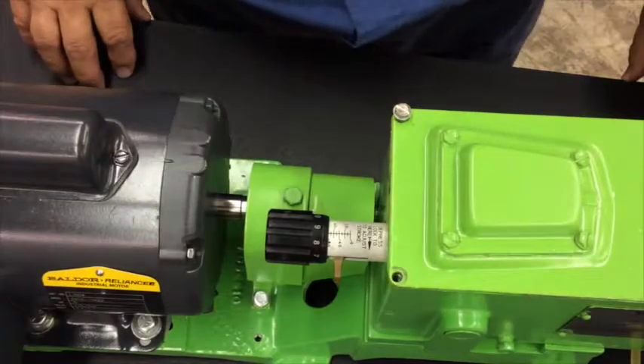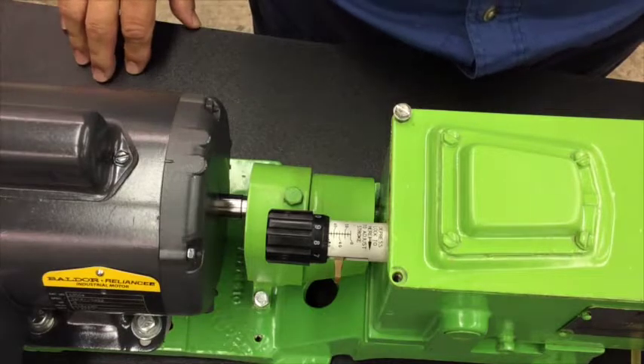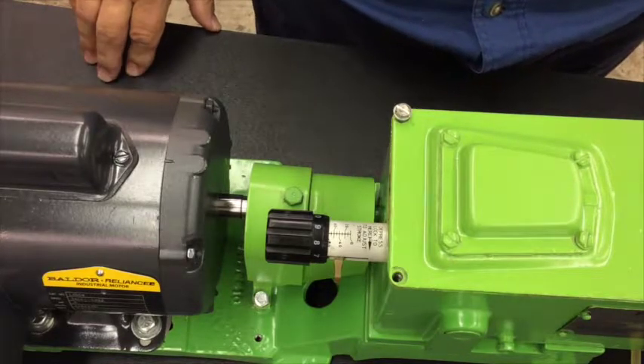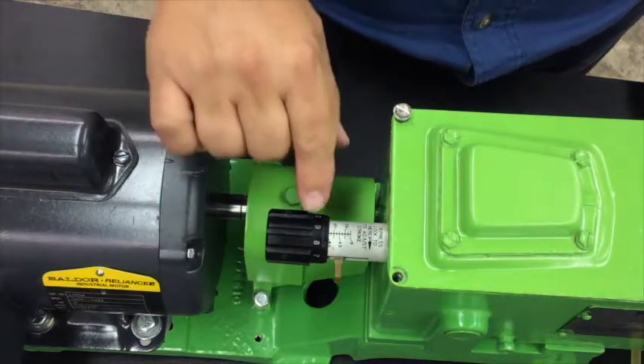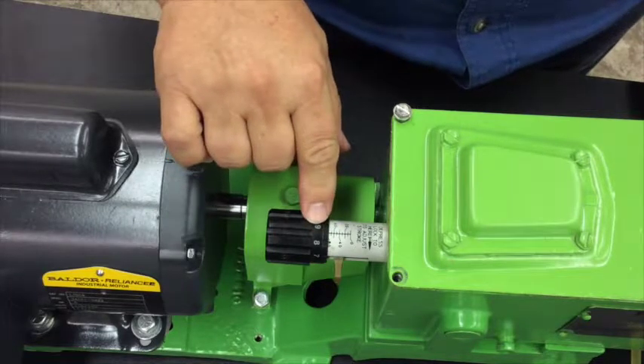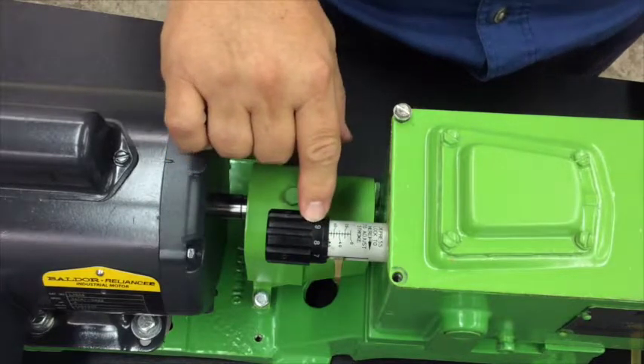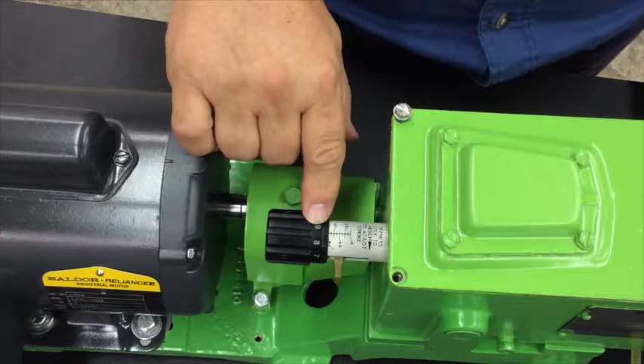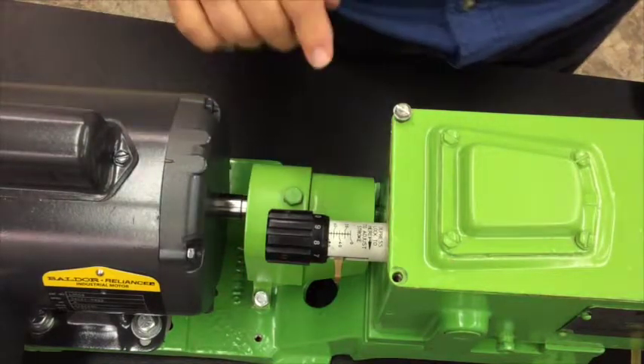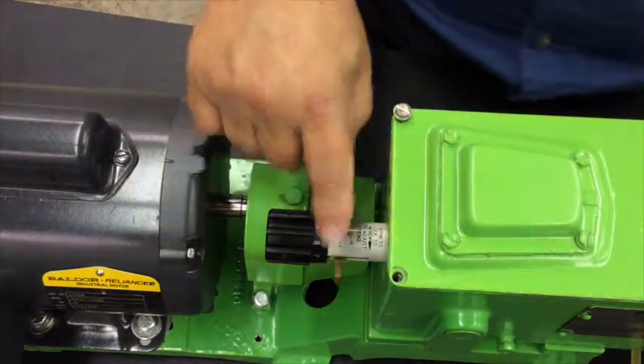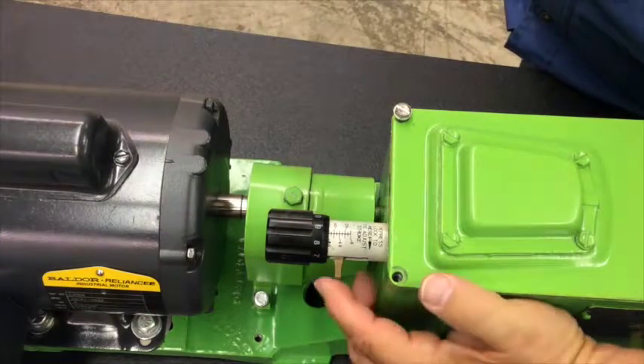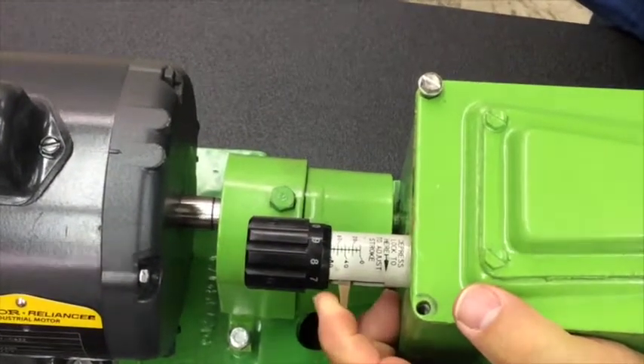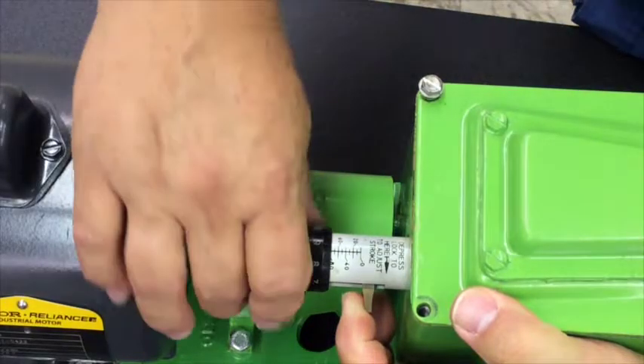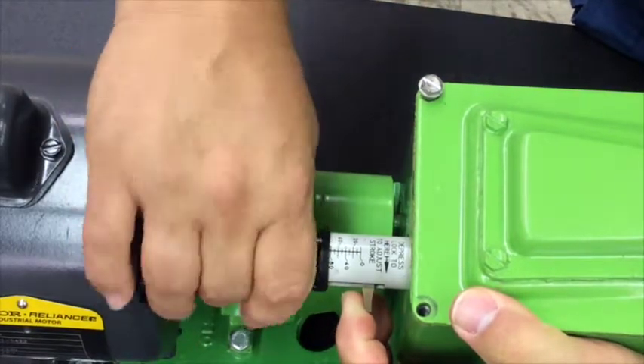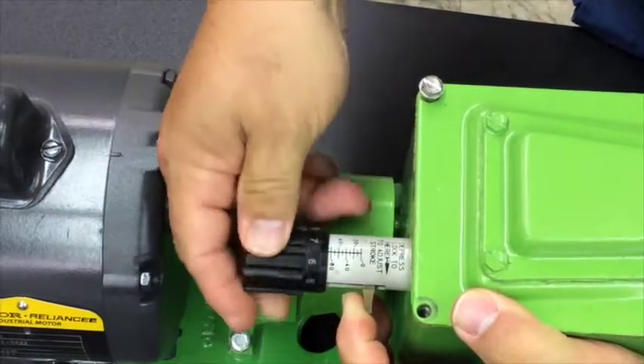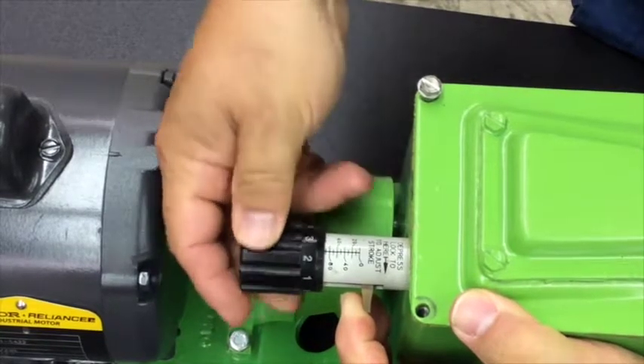All right, first thing I'm going to do is adjust the stroke to 100%. But before I do that, I want to make note of what the current stroke setting is so that we can return this pump back to its original stroke setting. To make the adjustment, I need to unlock the stroke setting. So I'm going to reach around here and pull the lock forward like that, and now I can adjust this to 100%. And here we go.